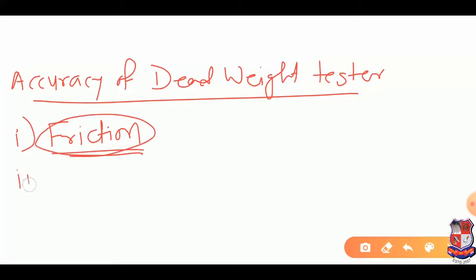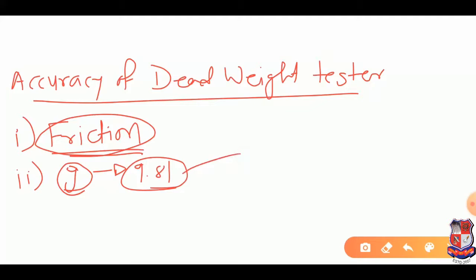Second is uncertainty in value of gravitational constant, which means G. The dead weight tester is calibrated initially by manufacturer for particular value of G. Suppose we take G as 9.81, but the local value of G is different from this. Hence, the correction should be applied according to that for better accuracy.